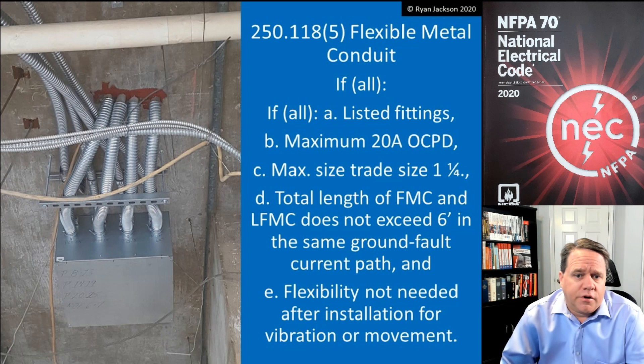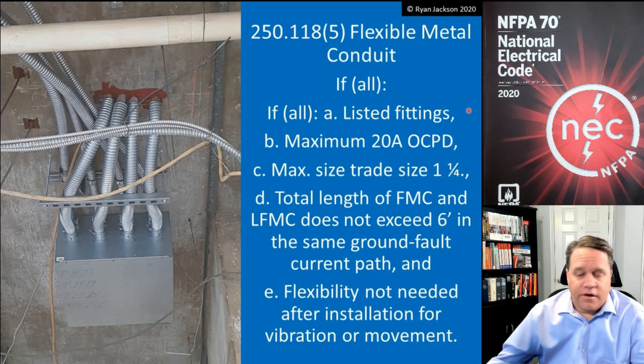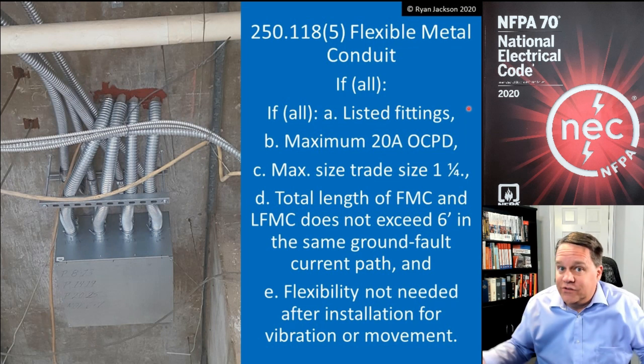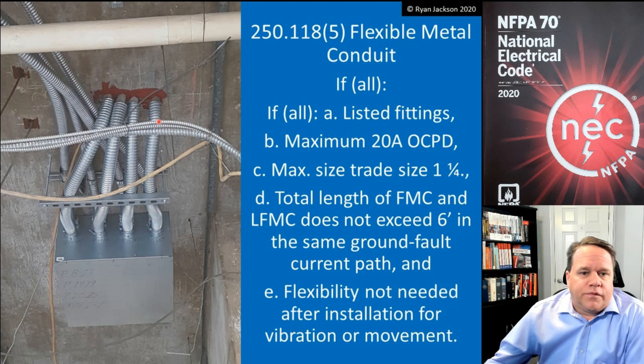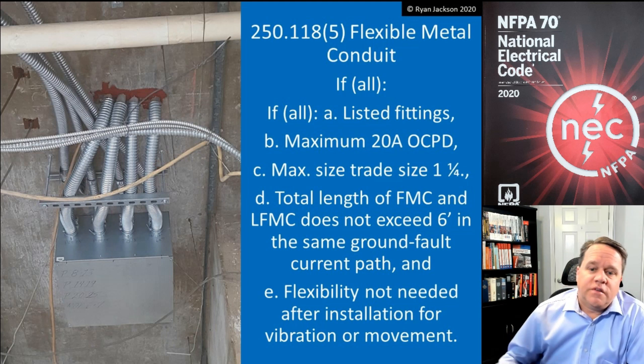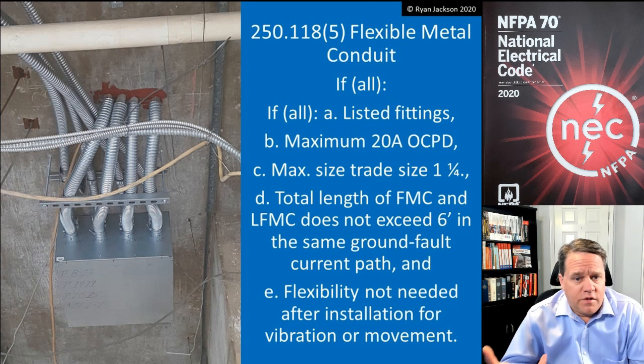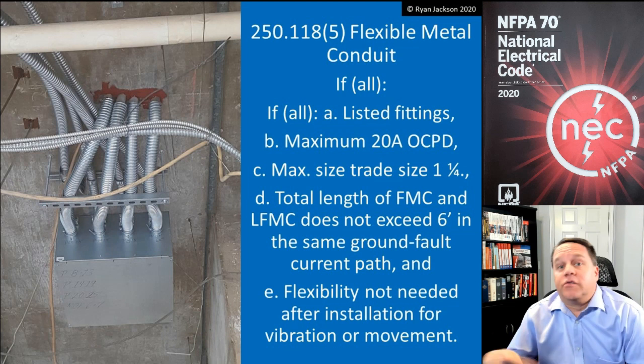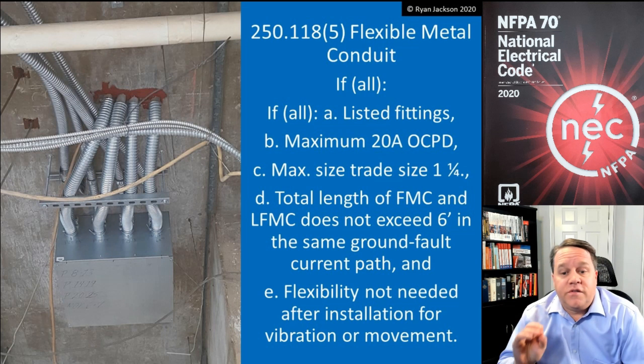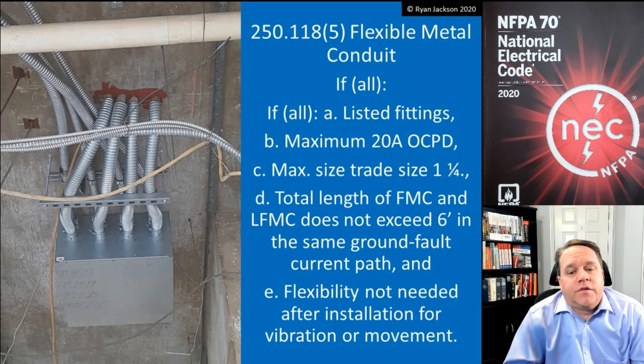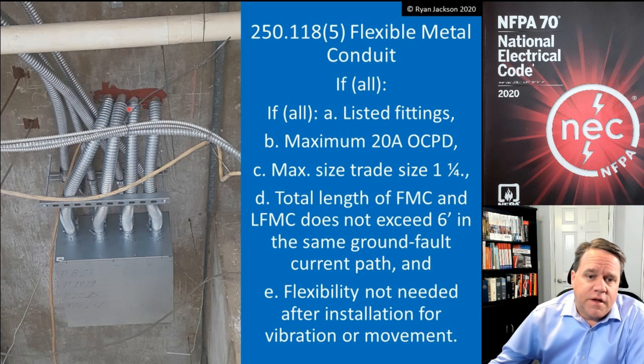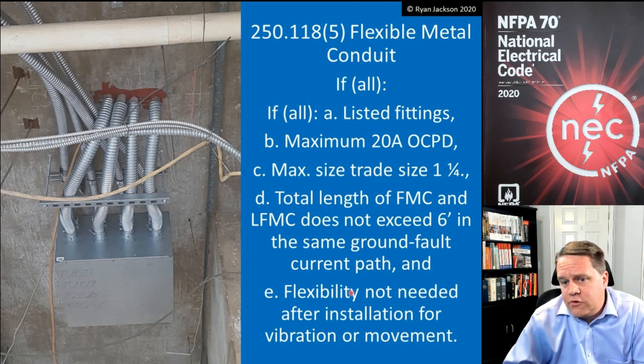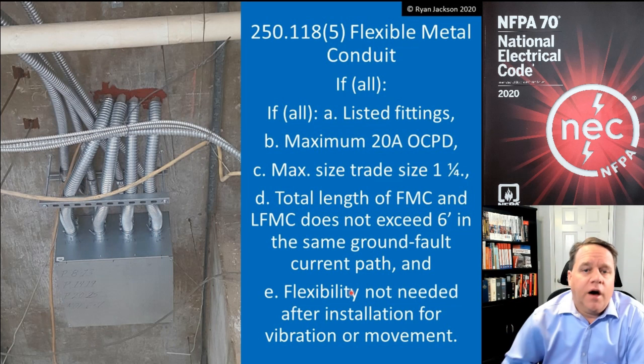We can use flexible metal conduit as the equipment grounding conductor if you meet all of these criteria: A) you must use listed fittings; B) maximum 20-amp overcurrent device; C) maximum 1¼-inch trade size for the raceway; D) the total length of flexible metal conduit plus liquidtight flexible metal conduit does not exceed six feet in the same ground fault current path; and E) flexibility is not needed after installation for vibration or movement. So if those conduits are less than six feet and you're using a maximum 20-amp overcurrent device, you do not need a green or bare wire inside.